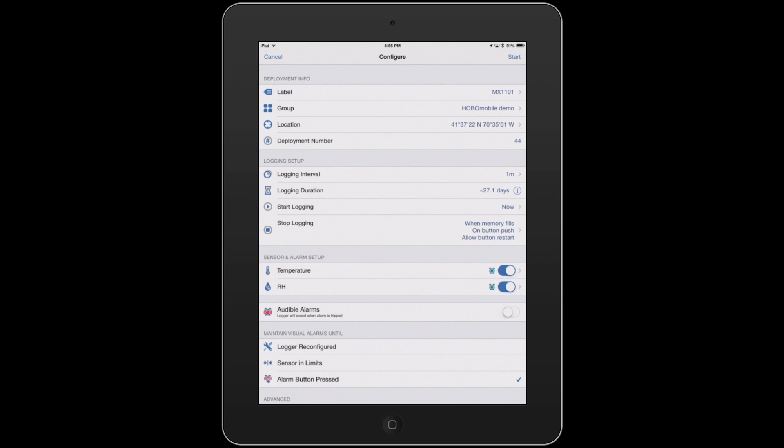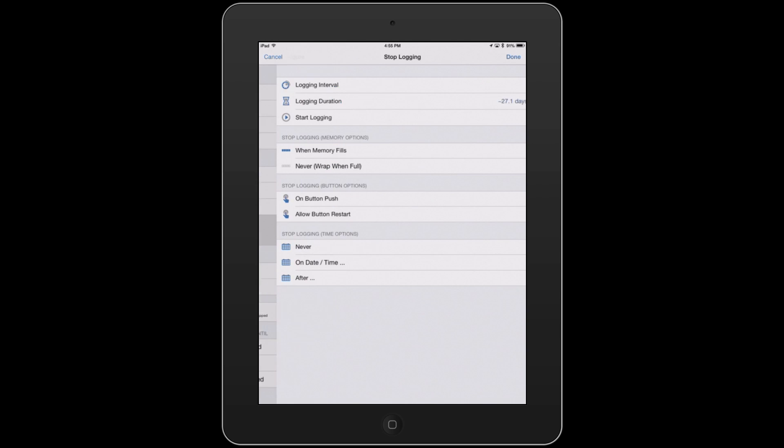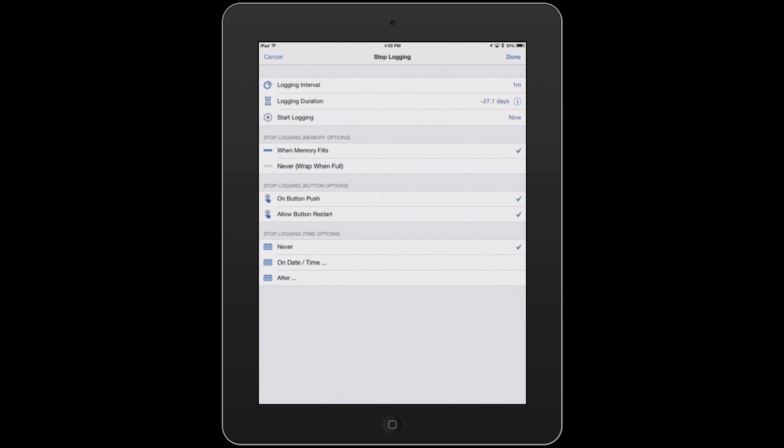And same with the stop logging options. You can have this set up so that it stops when the memory is full, or it never stops recording, so it overwrites the oldest data. You can stop it with the push buttons, whether through the Hobo Mobile app or on the MX-1101 itself.